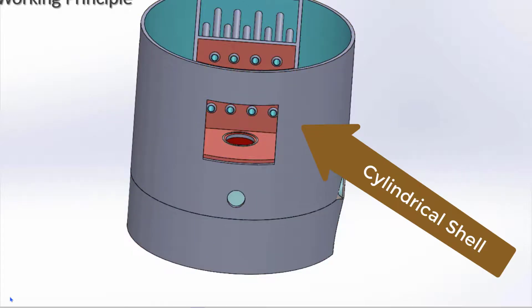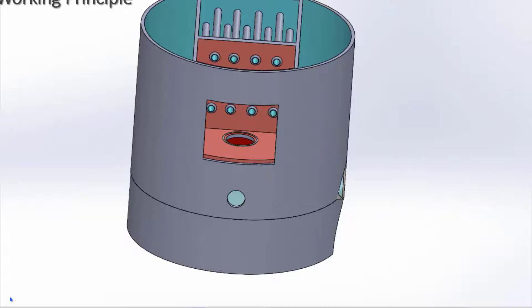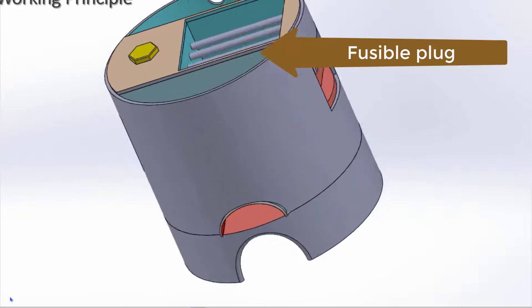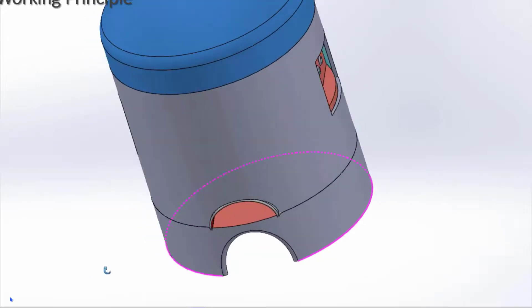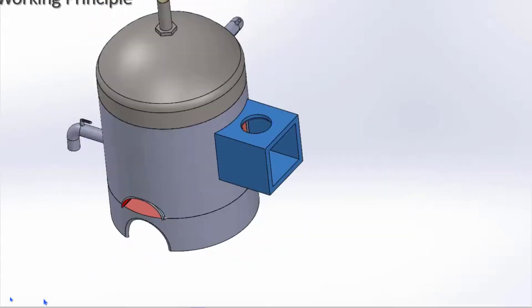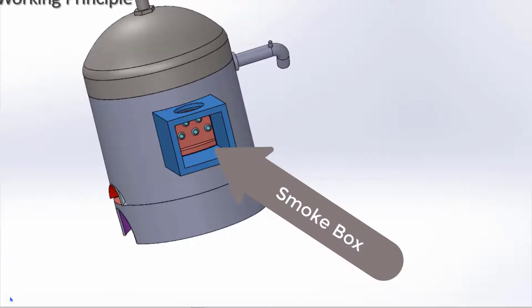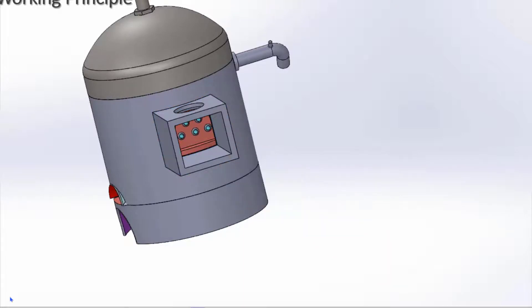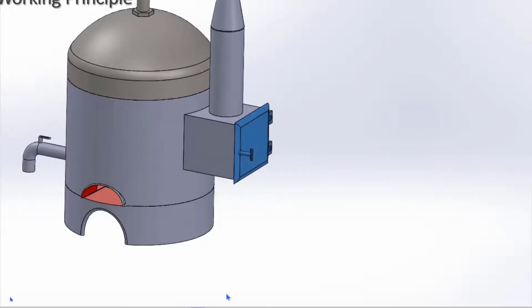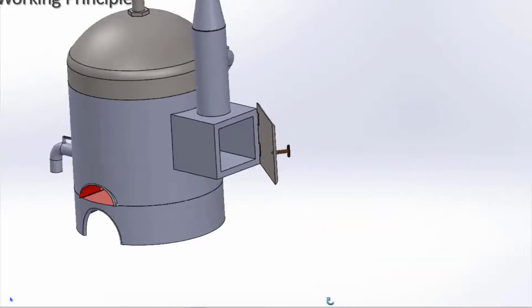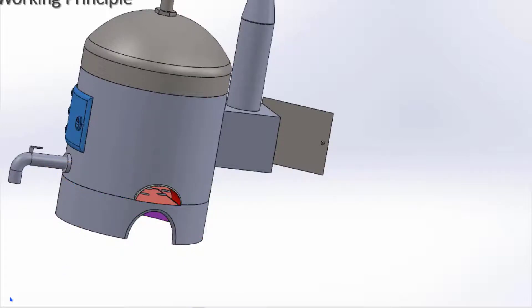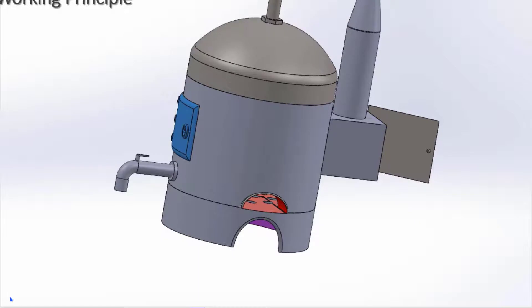The hot gases pass through the fire tubes to the smoke box. Look at the fusible plug above the combustion chamber. The upper part of the cylindrical shell is mostly occupied by steam. The smoke box discharges smoke to the atmosphere with the help of a chimney, and it is provided with a door for inspection and other purposes. There is another inspection door at the combustion chamber end.